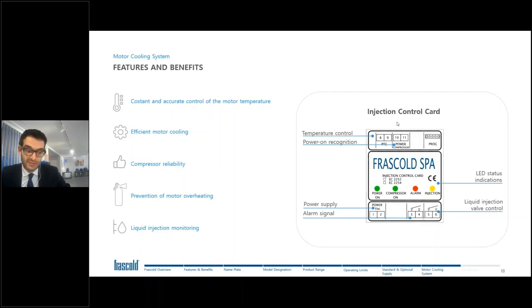If the motor temperature goes down, the motor becomes cool, I lock this fresh gas injection because I don't need that. I don't want the motor flange to become covered by ice. So I stop it. Instead, if the motor temperature is increasing, I open to inject fresh gas inside the motor. But if the temperature is still increasing, clearly I need an alarm signal.